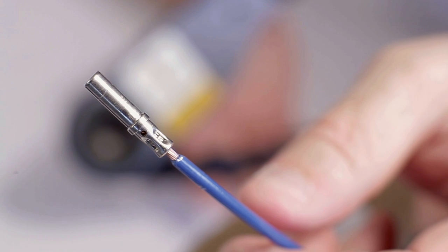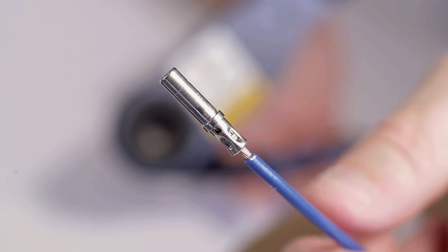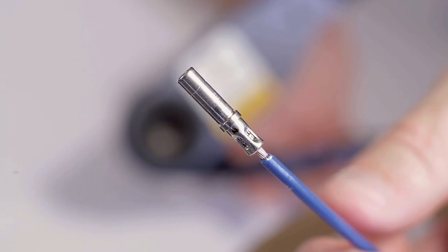A properly crimped wire will have the crimps high on the barrel and the wire should be visible through the inspection hole in the barrel.